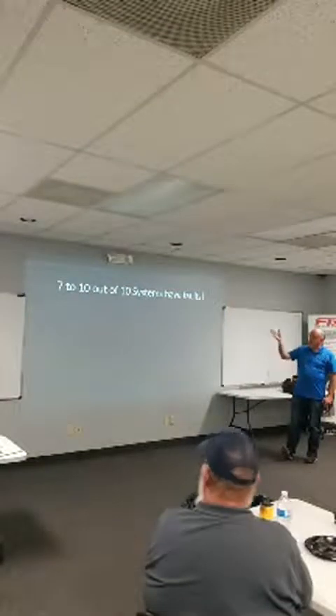So what happens to the capacity of your air conditioner? If I have to cool that warm liquid down and more of it goes to flash gas, I don't have refrigerant in my effective size evaporator. The effective size of your evaporator goes down. So it's going to go down, right? So all of these things, when you start looking at equipment, are things you're going to look at.